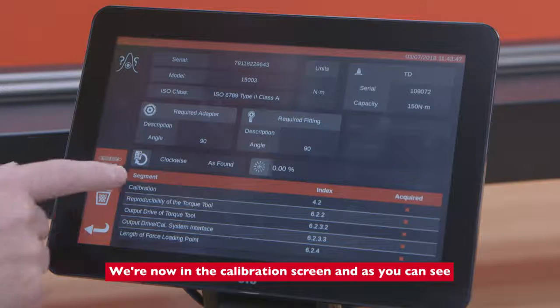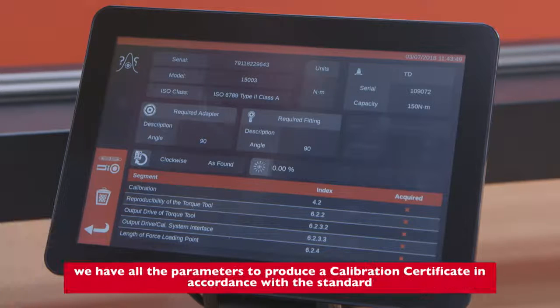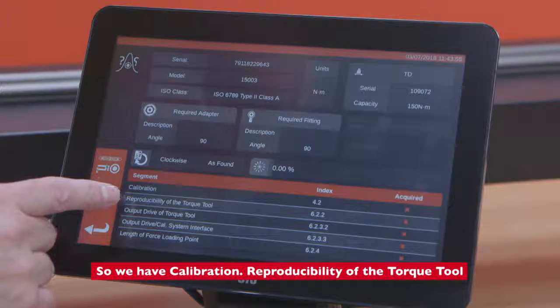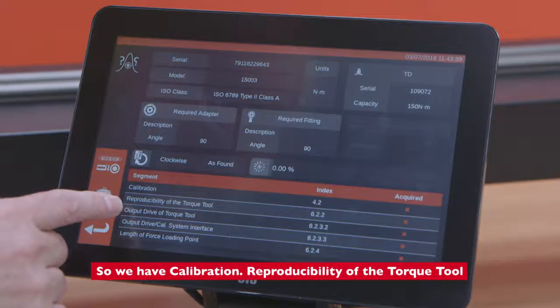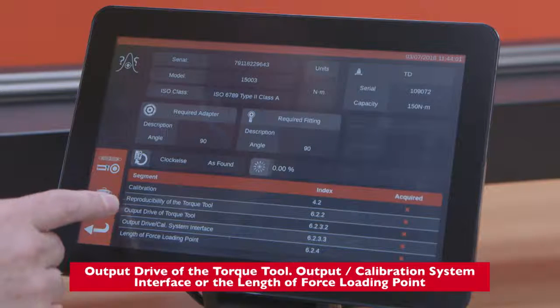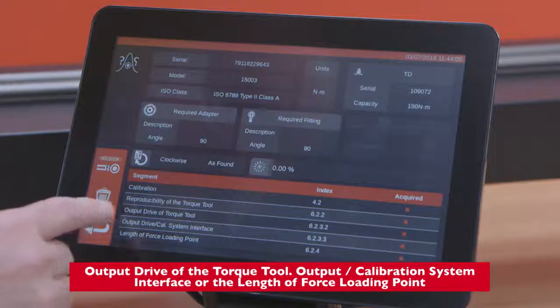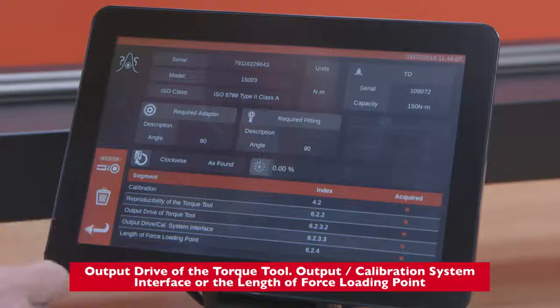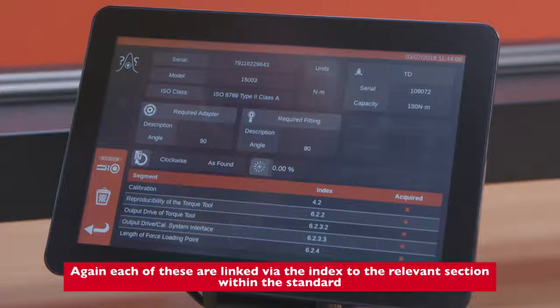We're now in the calibration screen, and as you can see, we have all the parameters to produce a calibration certificate in accordance with the standard. So we have calibration, reproducibility of the torque tool, output drive of the torque tool, calibration system interface, or the length of force of the loading point. Again, each of these are linked via the index to the relevant section within the standard.